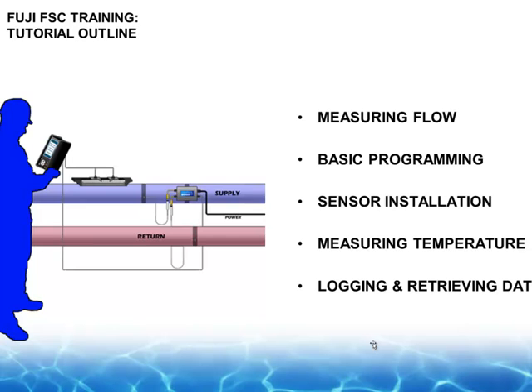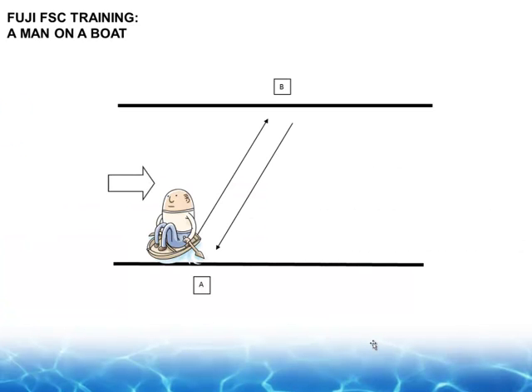In our program today, we are going to talk about measuring flow with the Fuji Portaflow, basic programming, transducer sensor installation, measuring temperature for those BTU applications, and logging and retrieving data. For those who are not familiar with the ultrasonic flow meter transit time theory, it's a unique technology where you basically take a sensor and clamp it or handhold it on the outside of the pipe, and it will monitor the liquid flow inside the pipe.